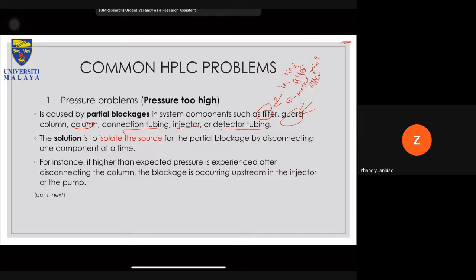So when you use samples, especially if the machine has been running for years and years, this problem, if it exists, is not a big deal. What you do is either change the filter, change the guard column, or even clean the guard column. A guard column can be simply cleaned by using a solvent that can dissolve most of the sample that you have analyzed previously. Say, for example, in my case, my sample mostly comes from a synthetic peptide source. So I know that my peptide definitely dissolves 100% in IPA, isopropyl alcohol.